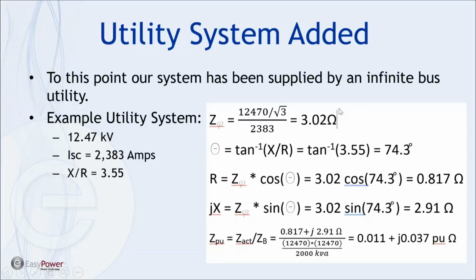Well, now once we have Z, impedance is effectively a right triangle when we have R and X in it. So the next thing we can do is calculate what theta is of our impedance triangle. That comes from the X over R ratio. It's simply the inverse tangent of the X over R that you're given. In this case, it turns out to be 74.3 degrees.